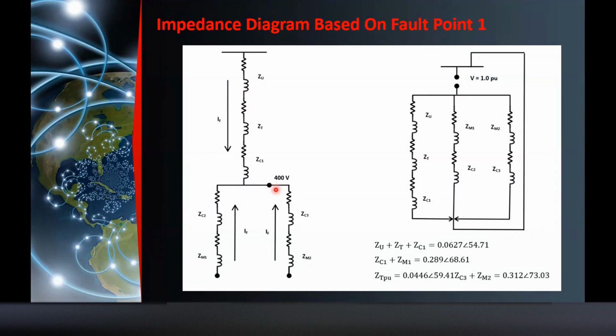So to get the faulted point, we need the impedance in per unit. Right? If this is the reference point and a fault occurs here, to size up the circuit breaker, the sources of the fault will definitely return to the source, plus these two, plus this one, feeder 2. ZU, ZT, and Z of cable 1 will be in parallel with the combination ZM1 and Z cable 2, and parallel to ZM2 and Z cable 3.